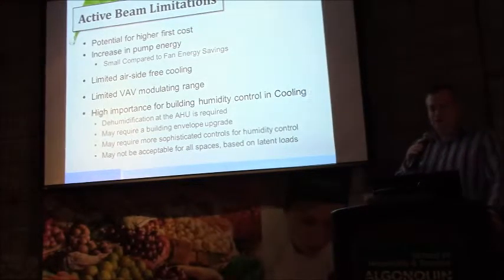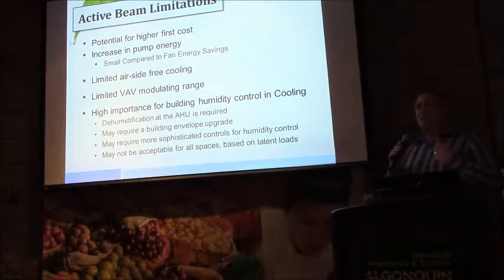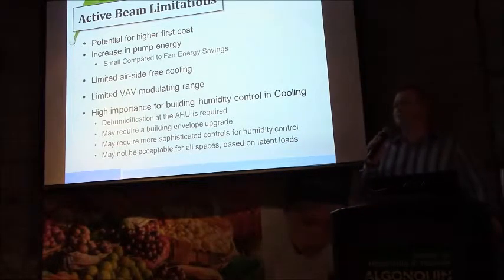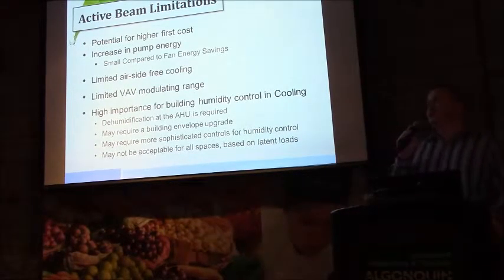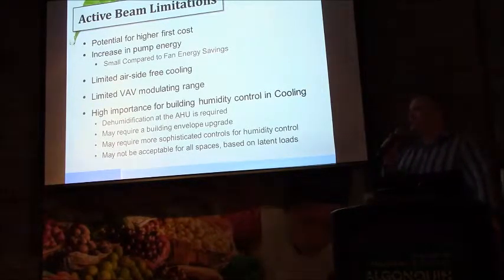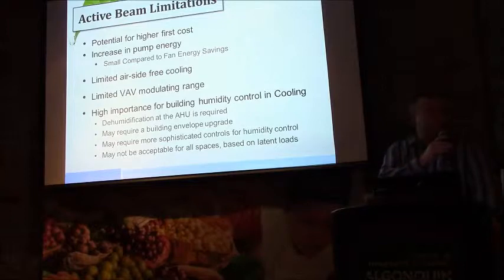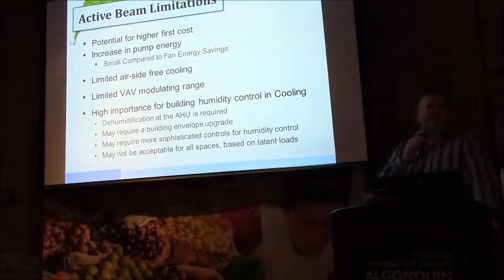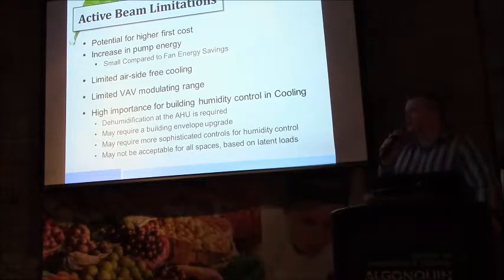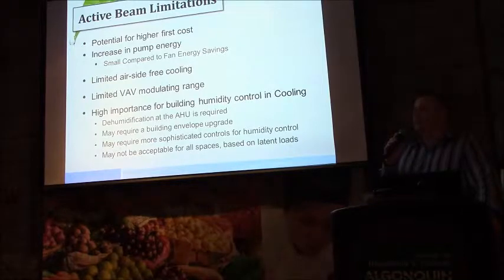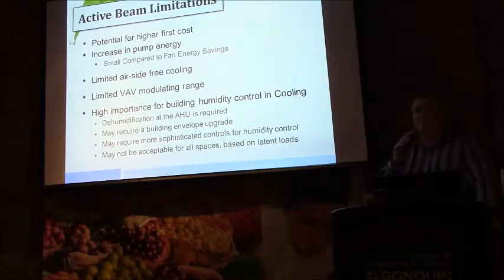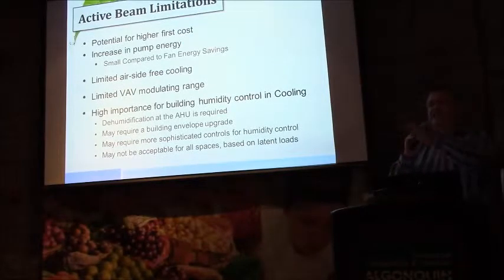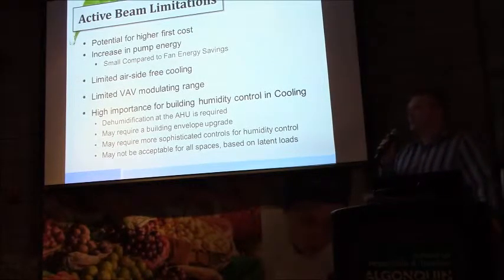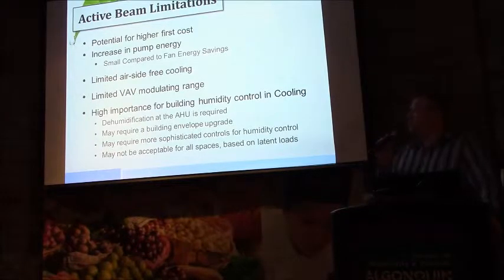There is increased pump energy, obviously, and the real crux, or the real opportunity for escalation in terms of costs, could come from piping costs for, say, a 4-pipe solution in the core, where conceivably some more innovative opportunities relative to piping and airside temperature control could be considered that may dramatically reduce the amount of pipe that needs to be hung to achieve that comfort level. Potentially a duct-mounted booster coil at the perimeter to reset the primary air in the winter season without spoiling the cooling capacity in the core, as a staged heating element, so that we have a little bit of extra heat at the perimeter where we'll lose it most, obviously.